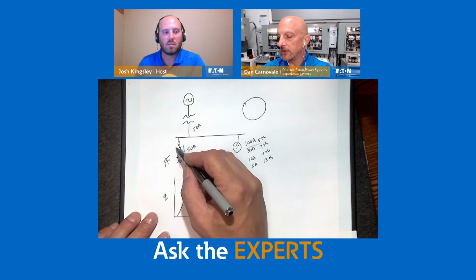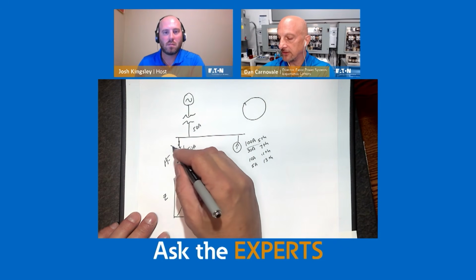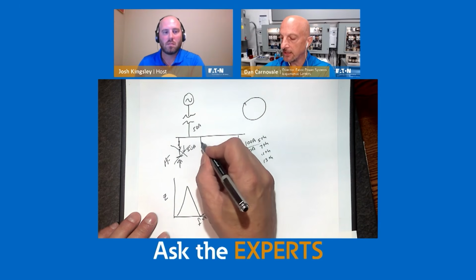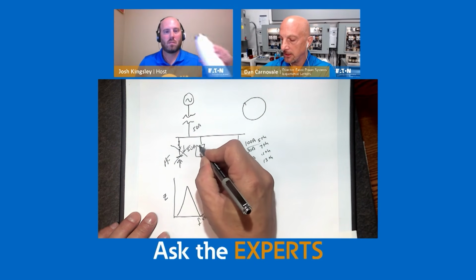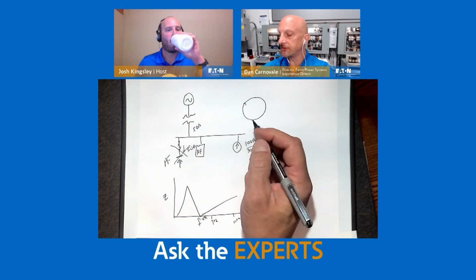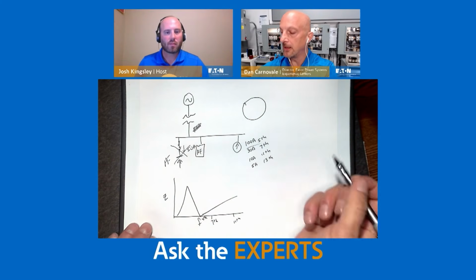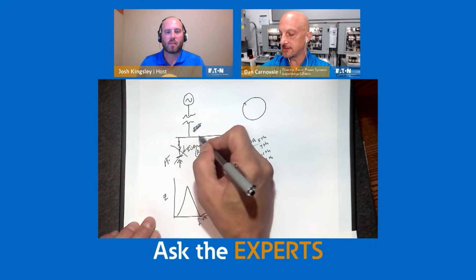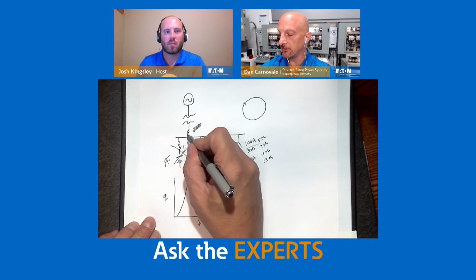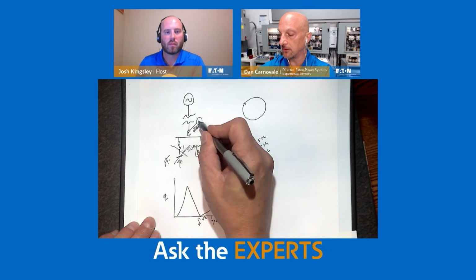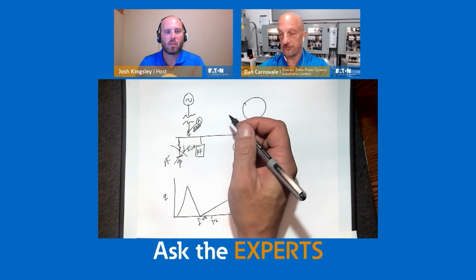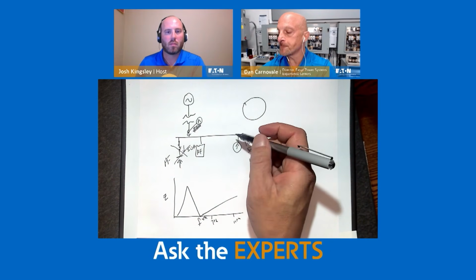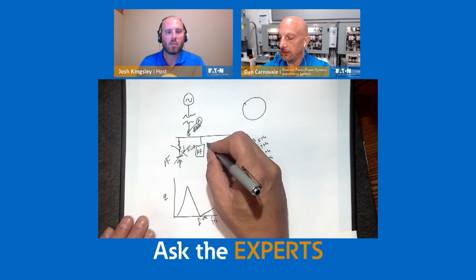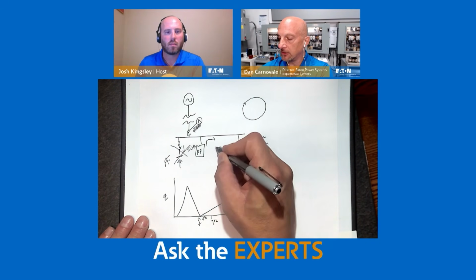Now, if I don't have this kind of filter, and let's just take this out for a second, I put an active harmonic filter in here. Active filter. Okay, now what does an active filter do? An active filter senses the current coming through the system, and a lot of times it'll sense it here with CTs on that main incoming line. And then what it'll do is it'll inject equal and opposite currents this way.